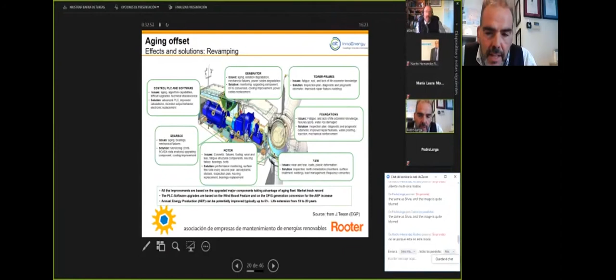For the generator, our main issues up to now are related to isolation degradation. We also have mechanical failures, mainly with bearings or slip-rings, and degradation in the power cables. For that, we will have to improve monitoring in order to extend the life from 20 to 30 years, as well as the cooling system.